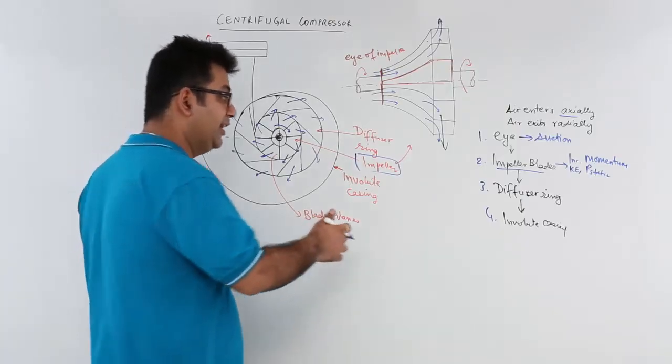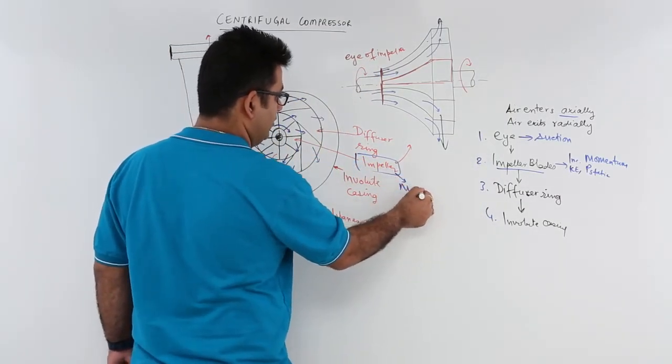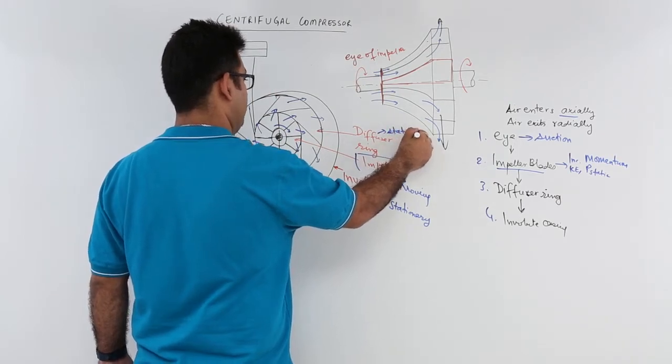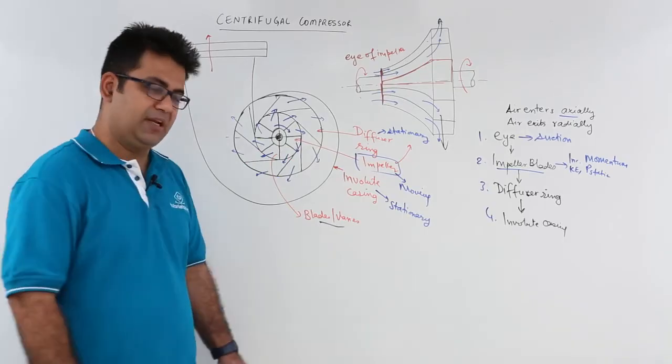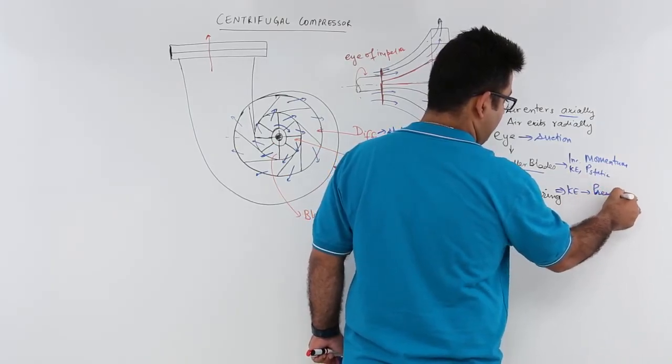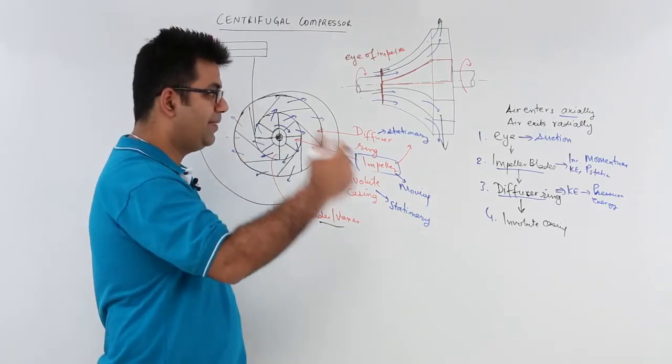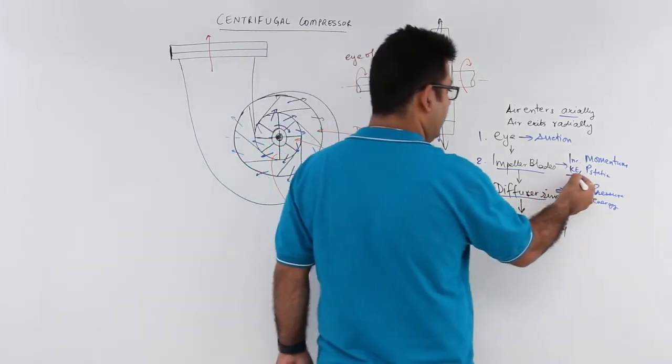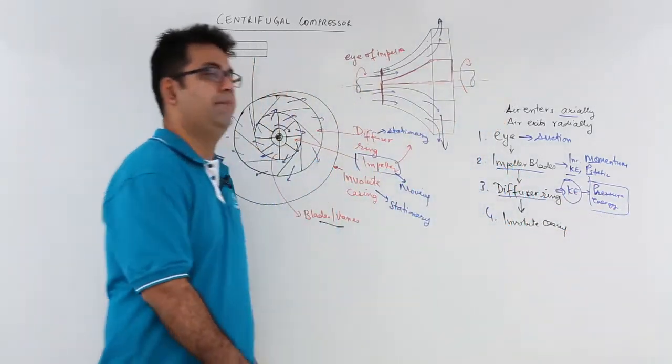Now from this impeller, they are taken into the diffuser ring. Now diffuser ring is static. So this impeller, this is a moving part, this is rotating. This is a stationary part, and so is this diffuser ring. So in the diffuser ring what is happening? All this kinetic energy, all this momentum is broken down, and this kinetic energy is now transformed into the pressure energy. So the pressure increases in the diffuser ring. It is not increasing in the impeller blades or the impeller. Impeller just imparts the energy which increases the velocity, the momentum, and the static pressure. And all this high energy is taken into the diffuser, where this high kinetic energy converts into high pressure energy.